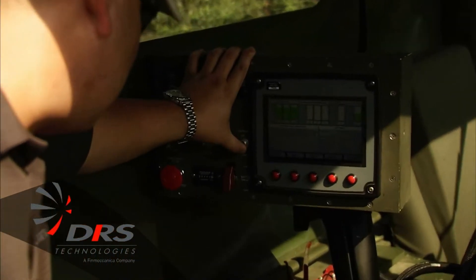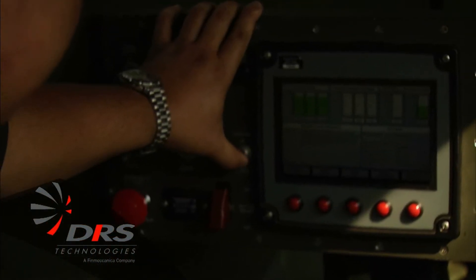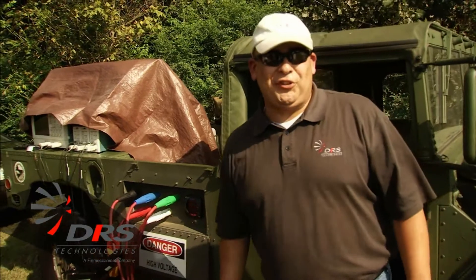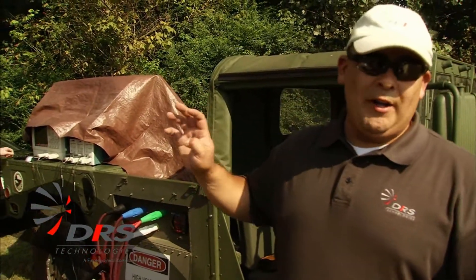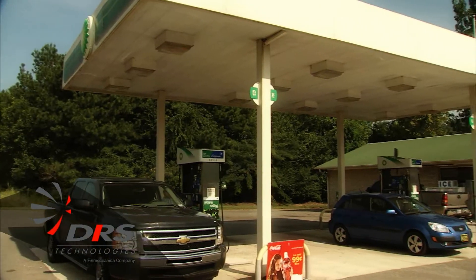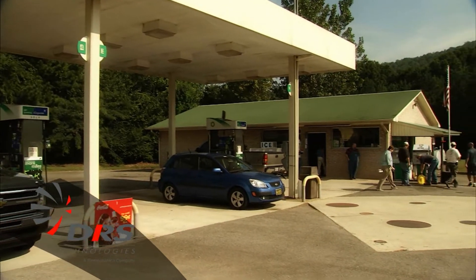Okay, we've got power. We're going to increase the voltage. What they're going to do now inside is use the flip breakers one by one. What we're doing now is just looking at the load. We have a 20 kW capability, and on average this particular store uses about 10 kW, so we should have plenty of power.